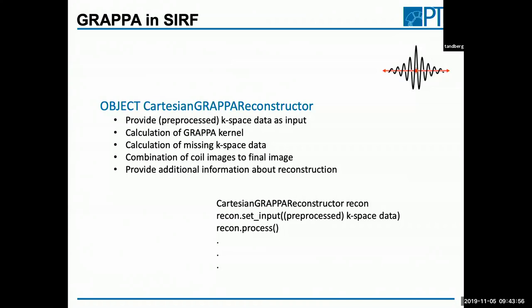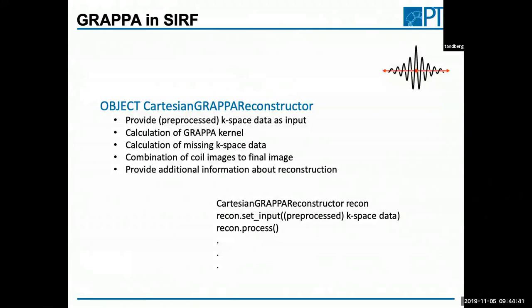Question about the coils: when you put one on the surface, is that just one coil? Clarification: these coils you put on actually have multiple receive elements. For example, the head coil has multiple rectangular receivers arranged all the way around the head. Commonly you might use eight receive channels in the head, going up to 32 or even experimental 64-channel setups. For cardiac imaging, you might use 32 channels — 16 at the front and 16 at the back.